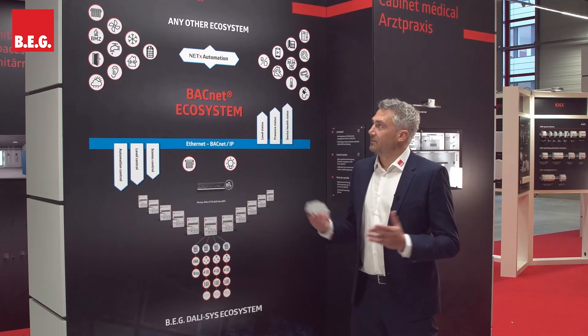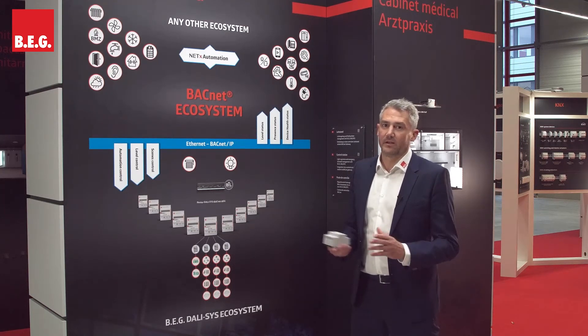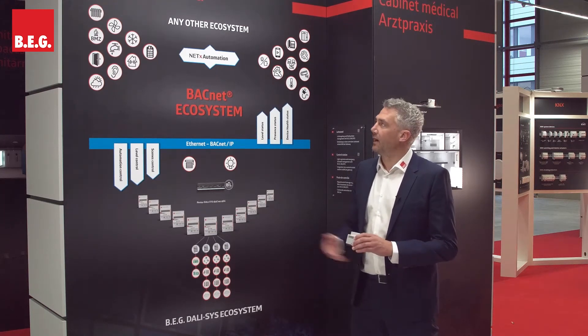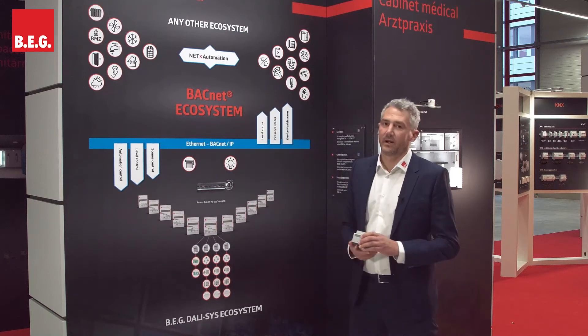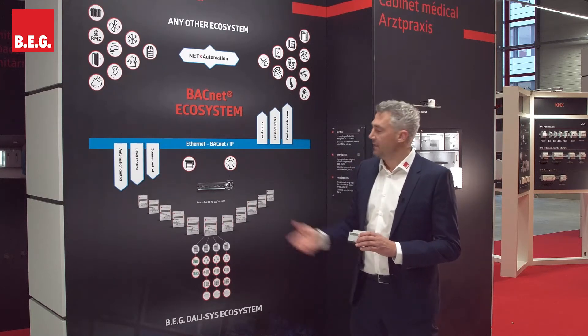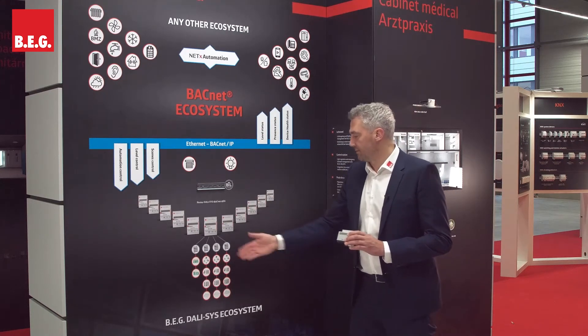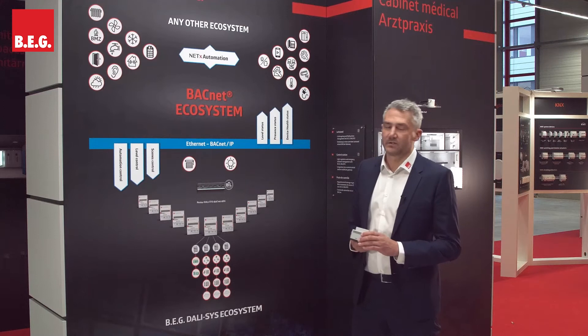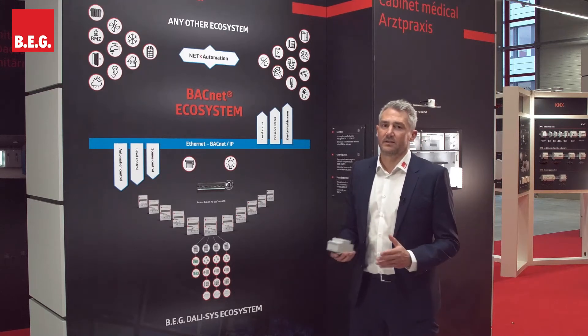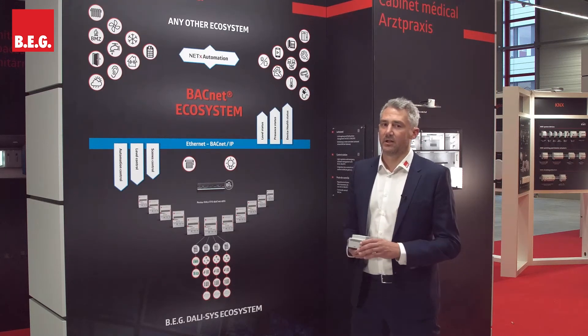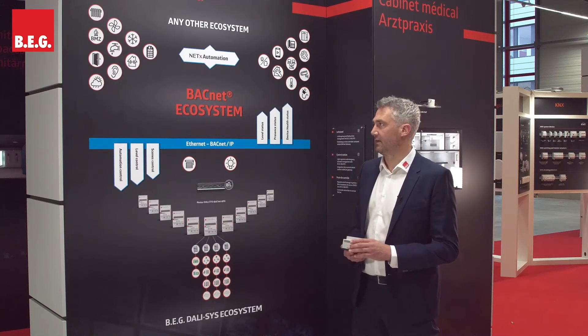As an example, there is the alarm system. If a break-in is detected, it is possible via a logical link and via the BACnet path in the lighting control, which is realized with the B.E.G. DALI-SYS, to ensure that the lights are switched on. This makes it more difficult for the burglar to escape.